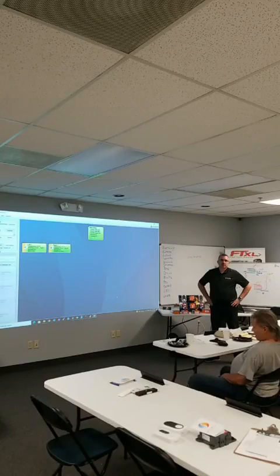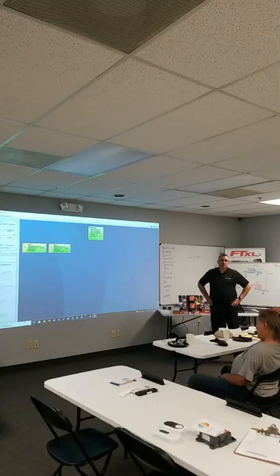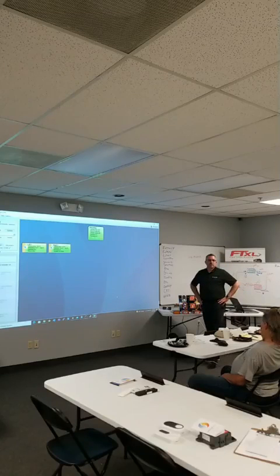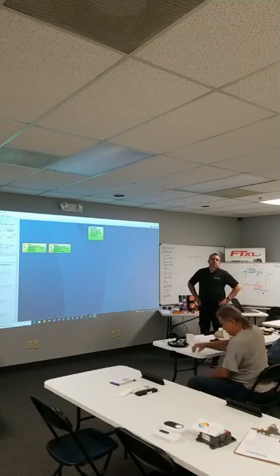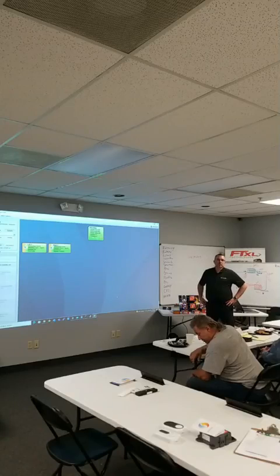What's the other one? Heat timer. Heat timer. Yeah, you can't change the temperature of the fluid, so you only let the fluid heat for a certain amount of time out of each half hour or each hour. Like a duty cycle type timer? Yeah, that's how they do it. But it's based on the outdoor air temperature, and sometimes they weight it with indoor air sensors too. But the key is to have that condensate sensor in there, so when the condensate heats up, that's when the cycle starts.